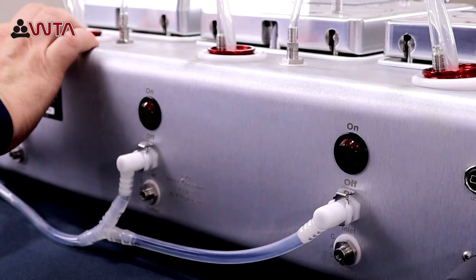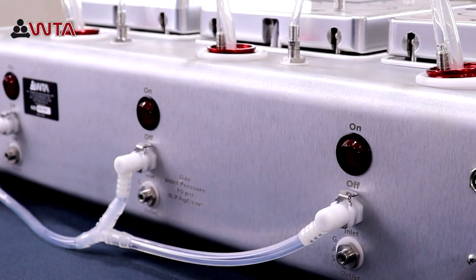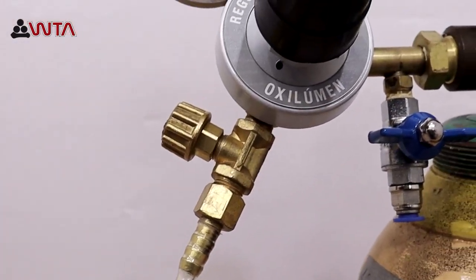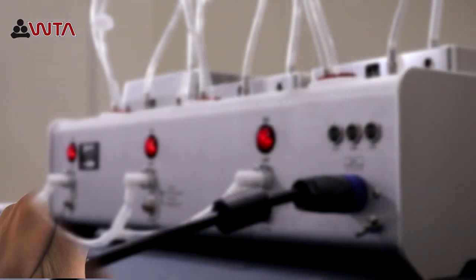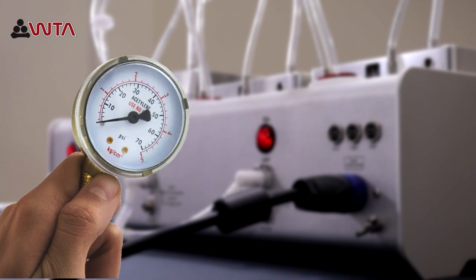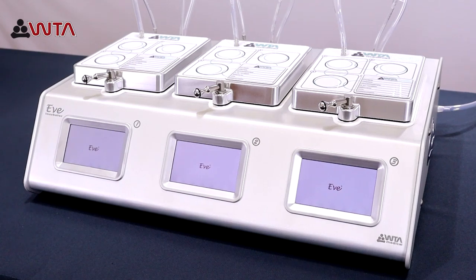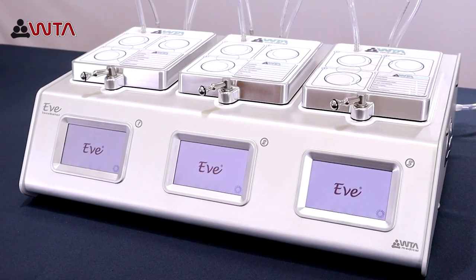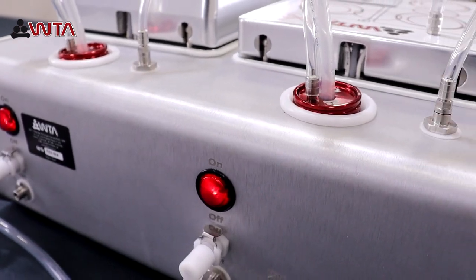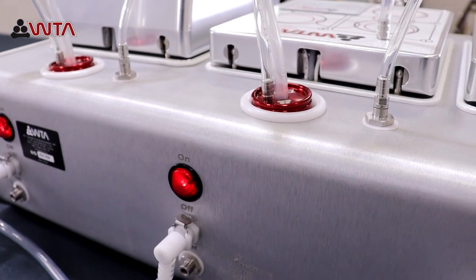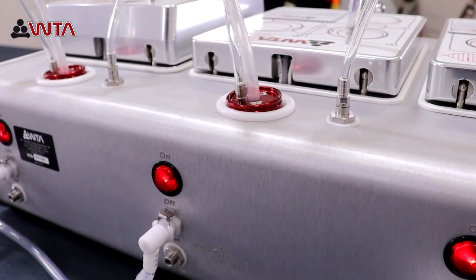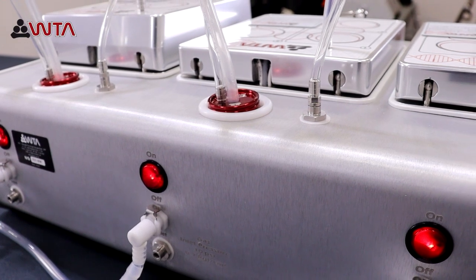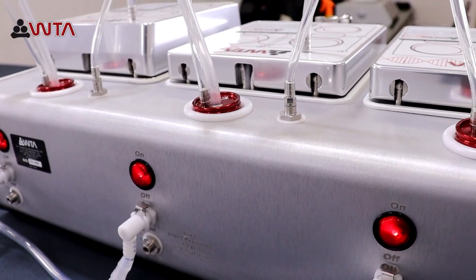The pressure regulator must be closed when connecting because the inlet pressure adjustment must be done with the incubator already turned on. The valves and tubing can be safely disconnected when changing gas cylinders without leaking or compromising the chambers, as they have a gas lock system. Installation is the same for all 3 chambers and the modular version, regardless of whether you have the standard lid or the high lid. After installing the hoses, it's time to turn on the incubator.